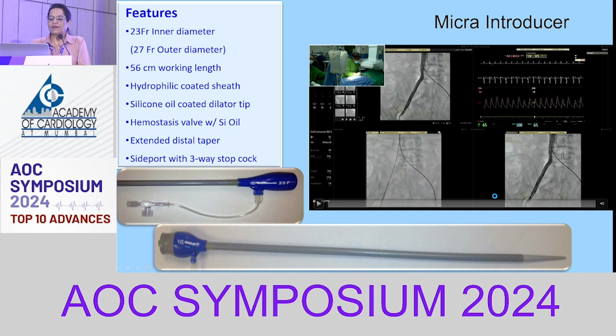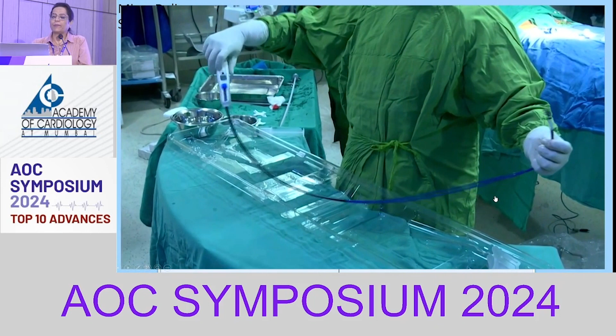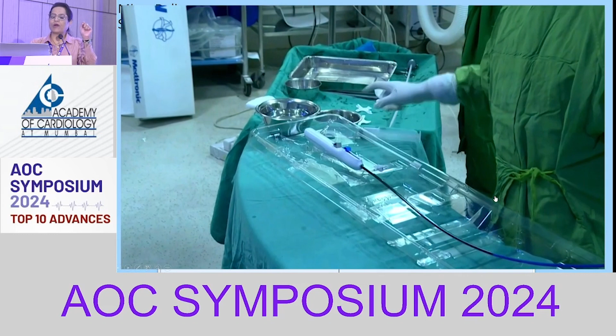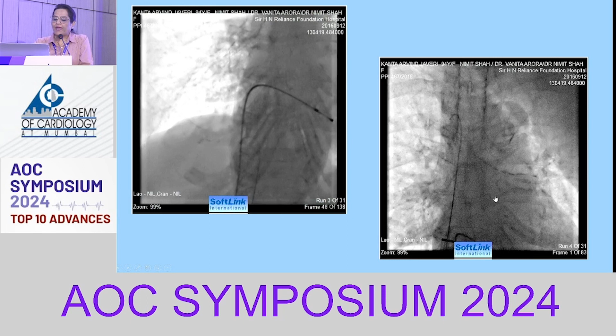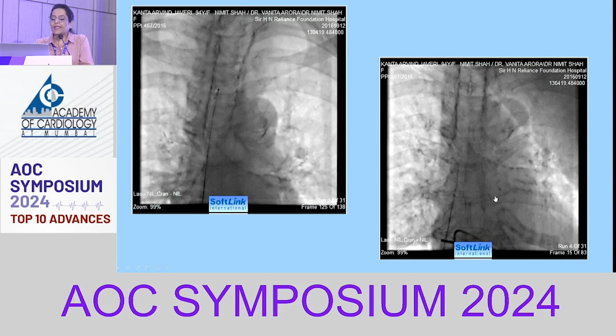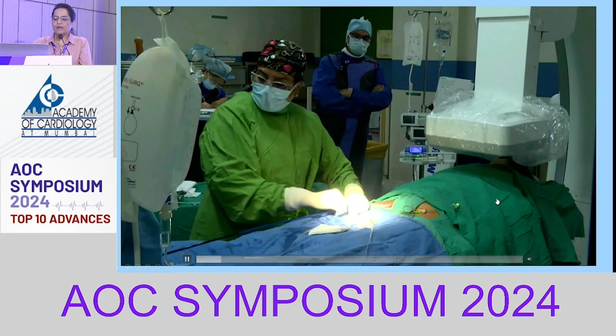The Micra capsule is mounted. This is how the leadless pacemaker catheter looks like, and this catheter has the leadless pacemaker mounted at one end. On this catheter there are 3 knobs. One is the deployment knob, the other is the deflectable knob, and this third green one is the locking knob. It is held on the distal end by the tethers. We place the stiff wire in the SVC as we do when we are doing BMV, and then we take the sheath in and place it in the mid-RA. Following that, we insert the Micra, or the leadless pacemaker, through the sheath and go up to the level of mid-RA. Once we reach the mid-RA with the leadless pacemaker, we pull down the sheath to the IVC, because there is only one curve of the leadless pacemaker, and it works better when you have the sheath in the IVC.